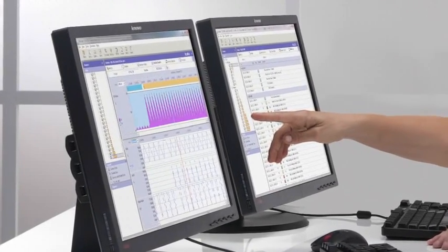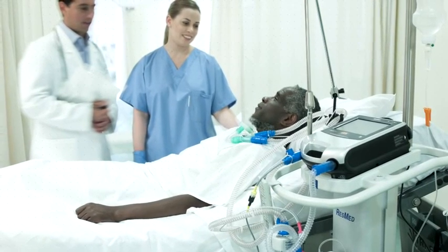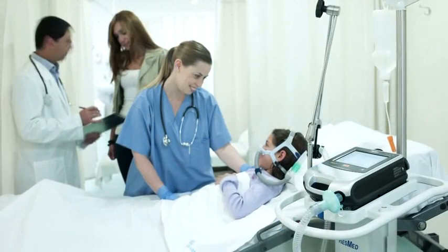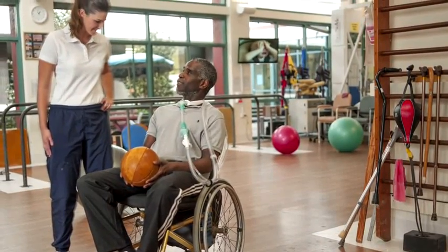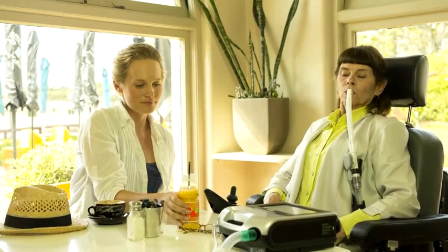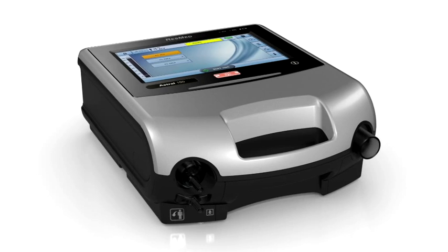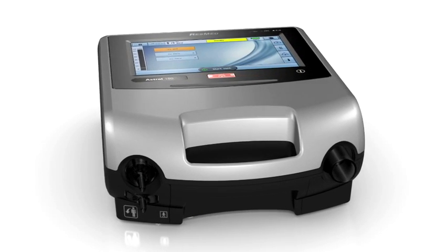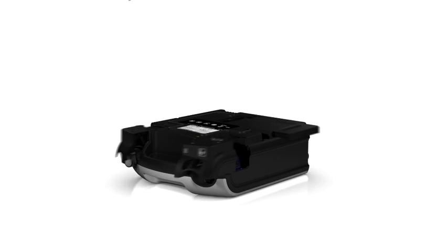Astral demonstrates that monitoring can be easy, insightful and in real-time. At the very heart of the Astral ventilator are simplicity and efficiency, enhanced by its versatility. From invasive to non-invasive ventilation, single circuit to double circuits, with intentional leak or valve, performing with non-vented masks, vented masks or mouthpieces, Astral meets an extensive range of ventilatory needs to simplify inventory management. Easy navigation with user-friendly menus enables quick and confident setup, saving time and helping you and your staff focus on what matters most. Its intuitive interface and user-friendly operation is designed to reduce the need for repetitive training and minimize training time. When it's time to service the ventilator, the pneumatic block can be seamlessly swapped during an in-field service or at the service center, reducing downtime for the device and improving cost efficiencies.